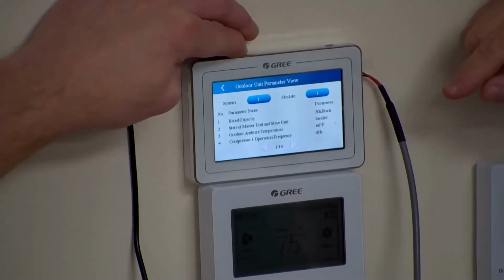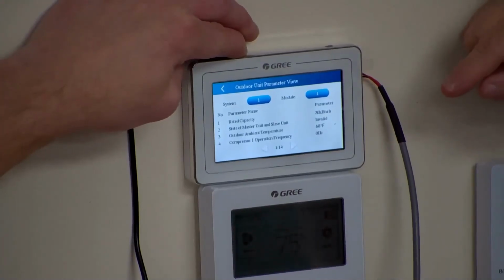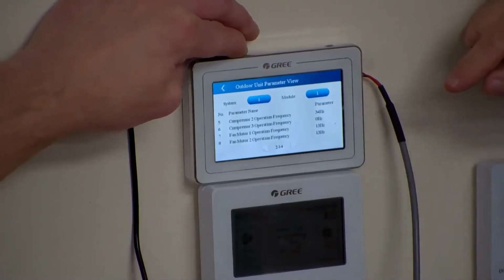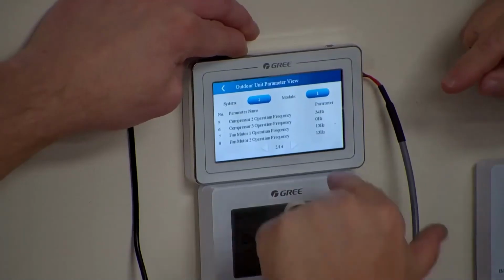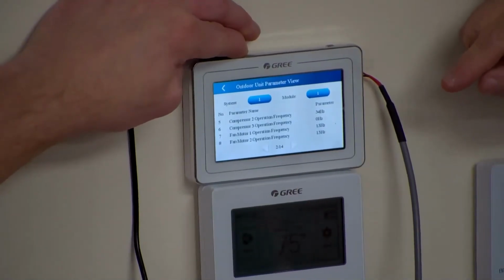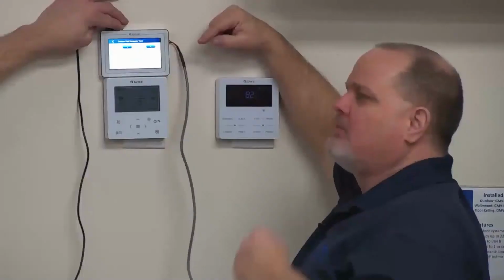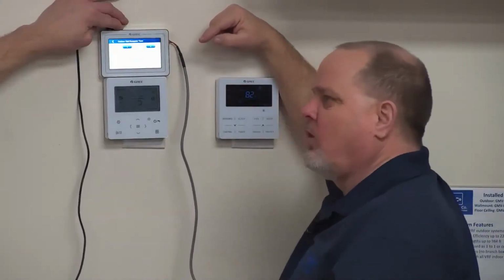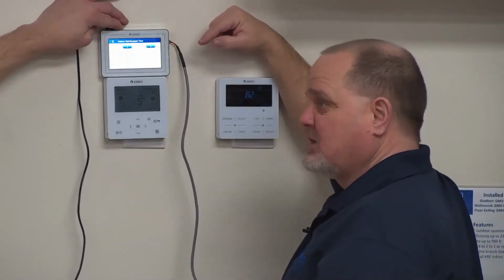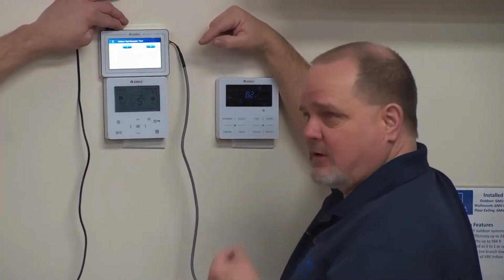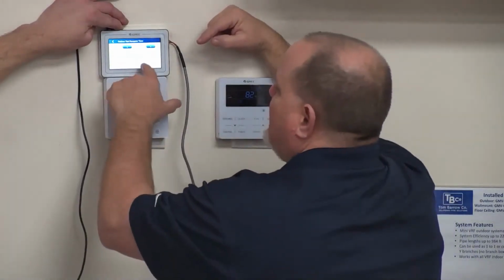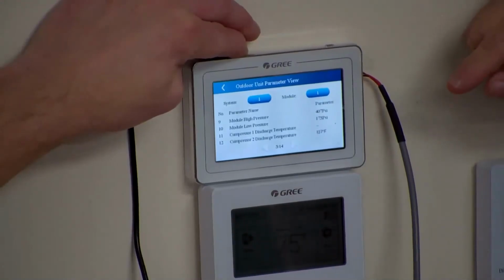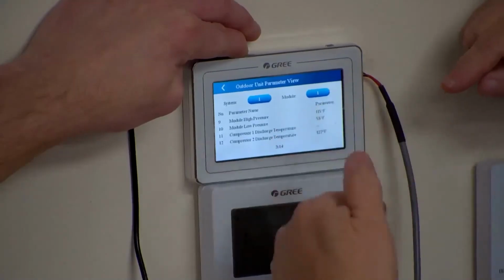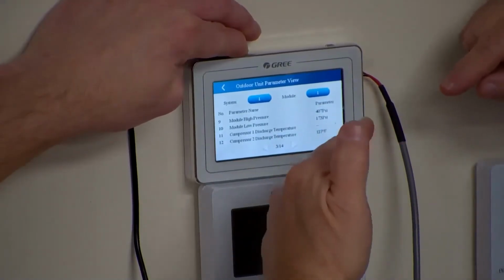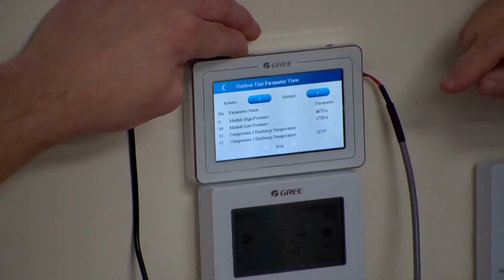If the outdoor temperature was 20 degrees, you would bet the fan speeds would be higher and the compressor speed would be higher, because I'm having a harder time absorbing heat into the outdoor coil in heat mode. Got to ramp up because I've got a colder outdoor temperature, okay? That's why I said you've got to start thinking like the machine's thinking so you can understand what the thing is doing. It gives me my high pressure and my low pressure, both in pressure and in temperature.